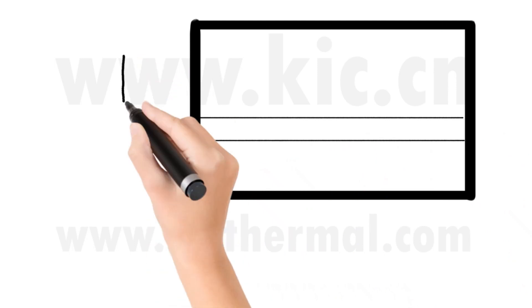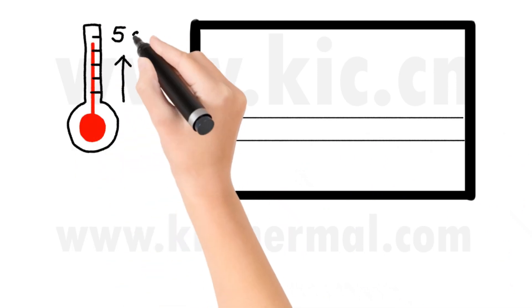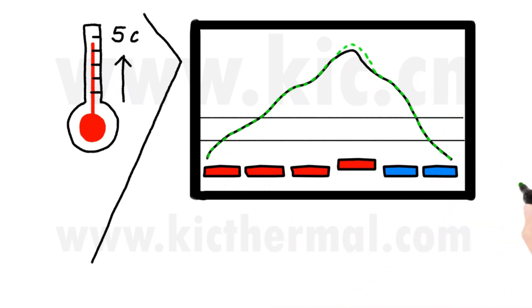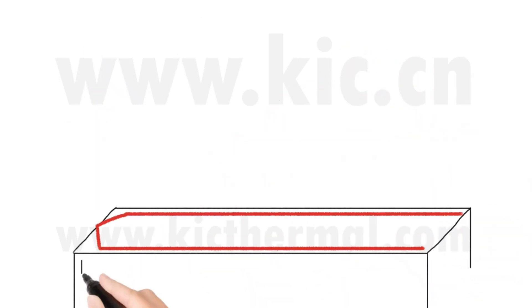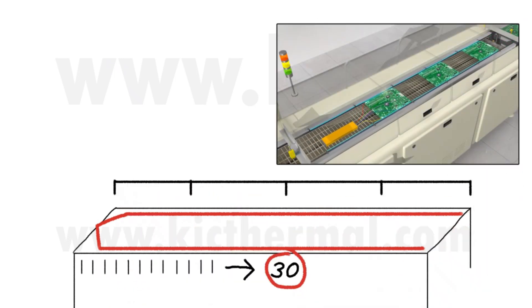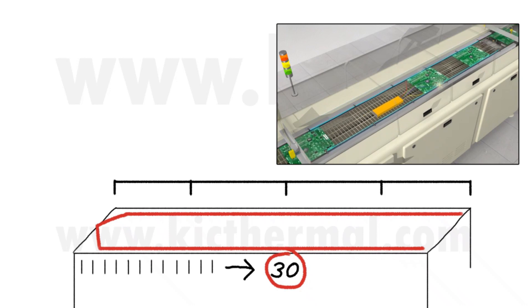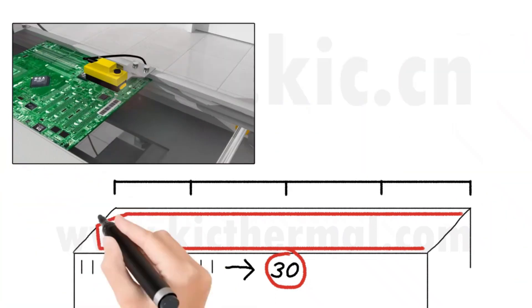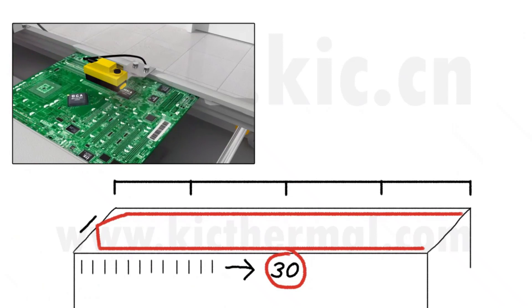Virtual profile is achieved by using the following hardware. For temperature measurements, the KIC Automatic Systems use a set of thermocouple probes that are installed along the rails, covering the complete heating area and part of the cooling. A total of 30 thermocouples provides a resolution of two or more per zone. They are installed close enough to the product to provide high levels of accuracy and allow us to detect even the slightest change in heat transfer to the product.